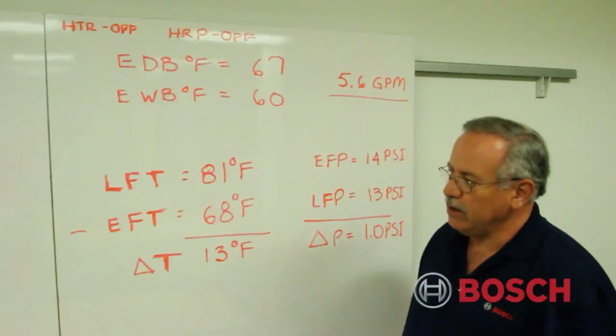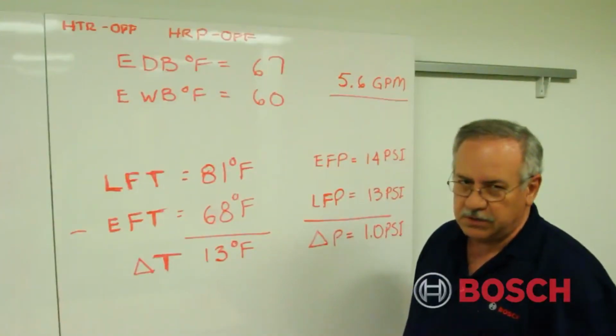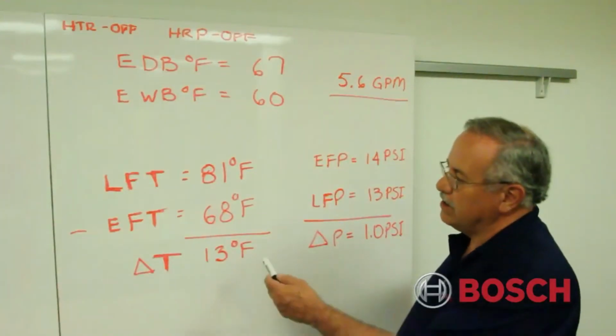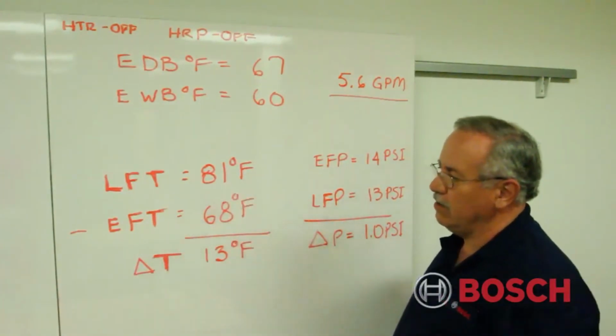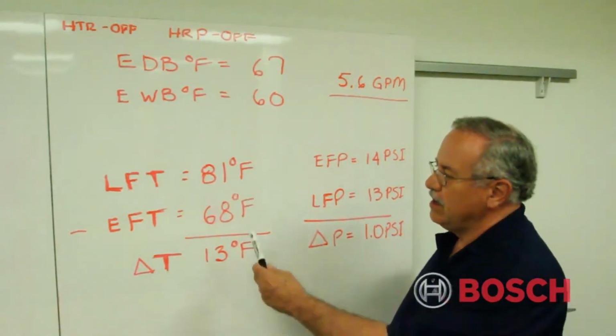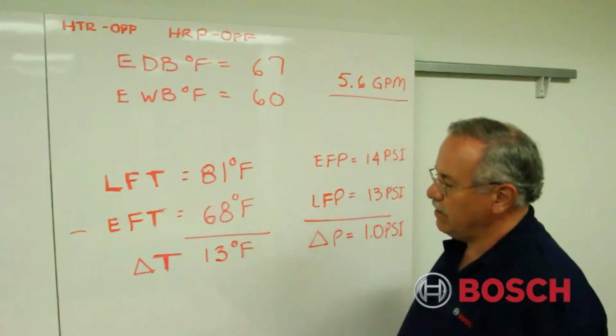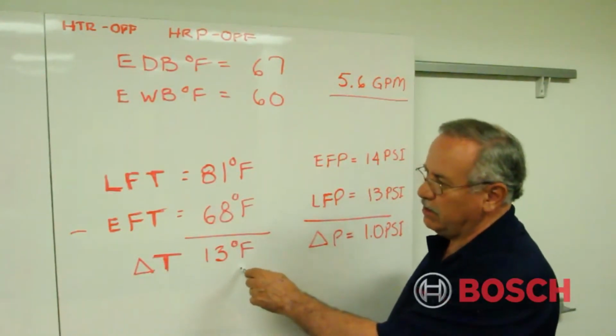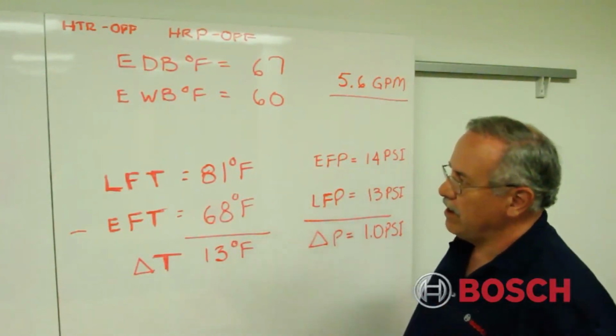As we're talking about cooling, we're absorbing heat from the structure and rejecting it to the earth. So the temperature should be getting hotter when it leaves the coaxial. So here we have a delta T of approximately 13 degrees. That's one of the three factors we're looking for.